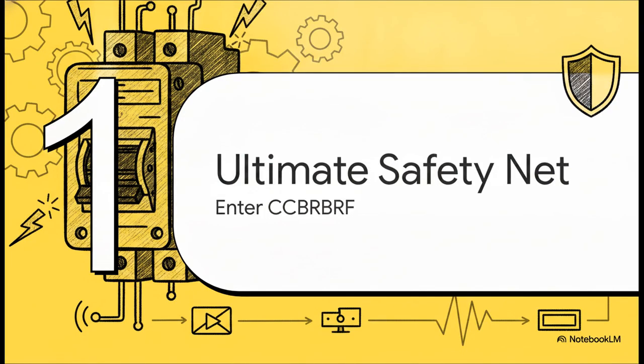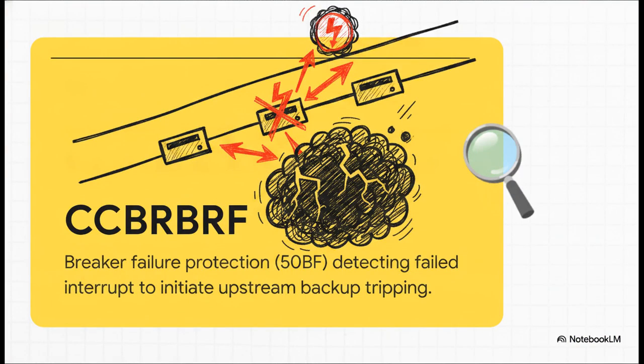Enter CCBR BRF, or if you prefer the ANSI standard, 50BF, the breaker failure protection function. Its whole job is to detect when a primary breaker fails to interrupt a fault after it's been commanded to open. When it spots this failure, it initiates a backup clearing process by tripping the upstream breakers. It's there because a stuck breaker would leave a catastrophic fault energized indefinitely. Without this function, a single mechanical failure could literally destroy an entire substation.